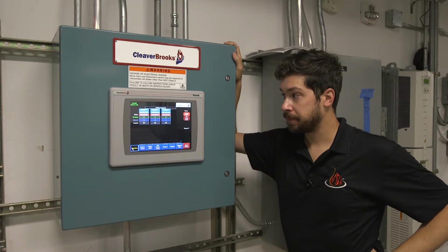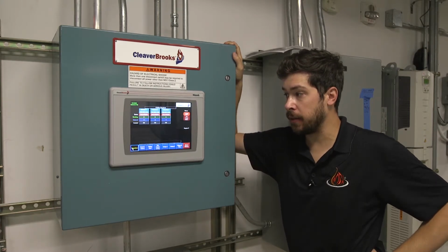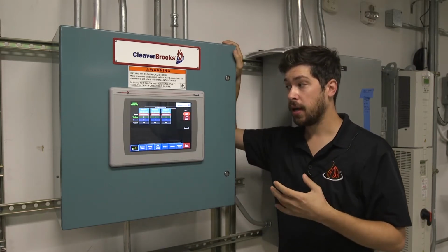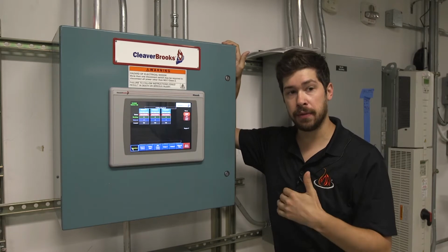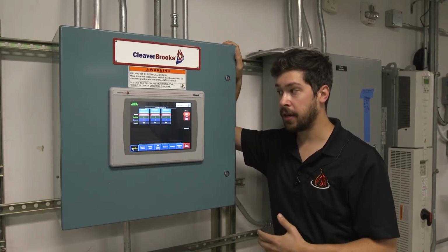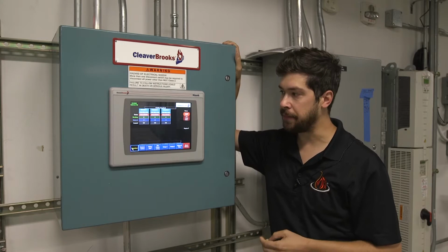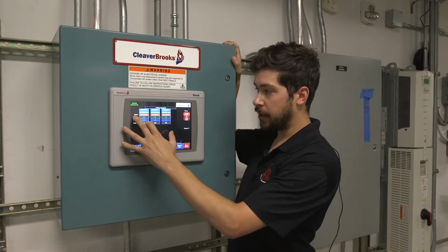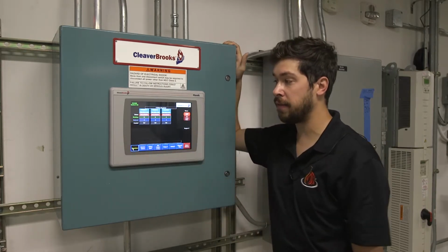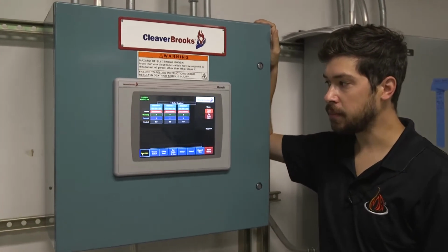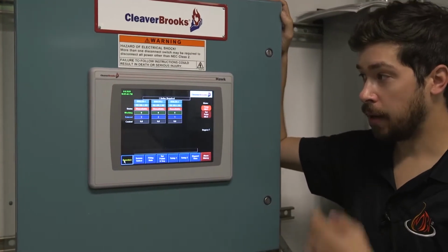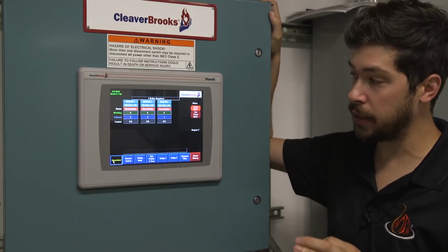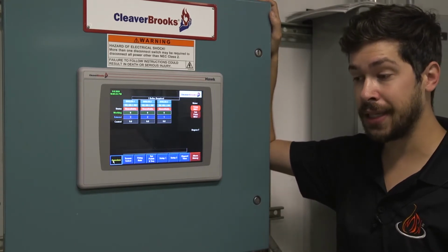Okay, just gonna talk about this panel here, which is the master panel, which is the one that's actually controlling each boiler in terms of which boiler fires, how hard they fire, etc., which order they fire in. Typically, you'll see here where it says status, currently it's saying all unavailables.